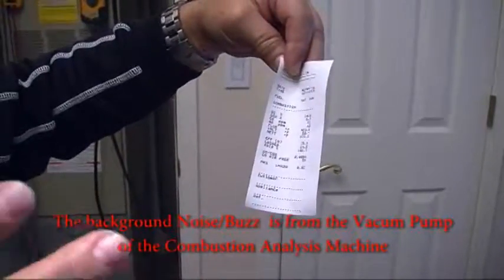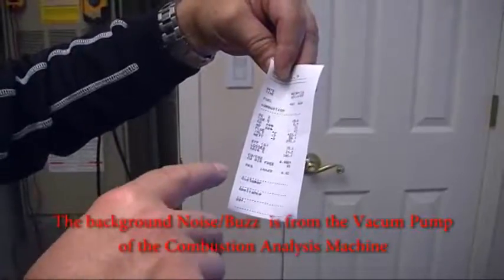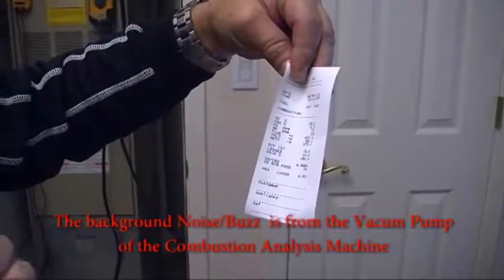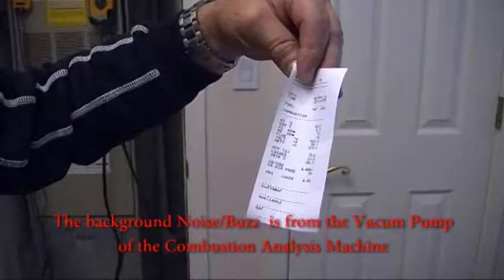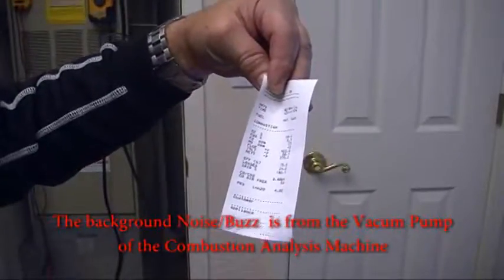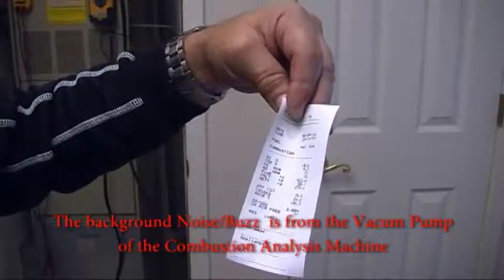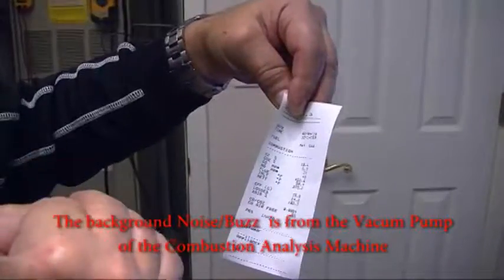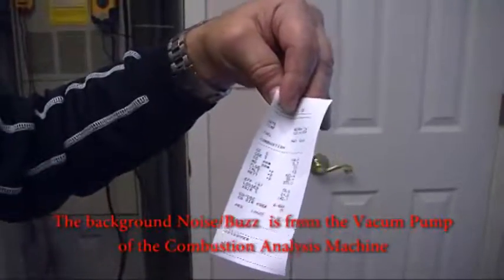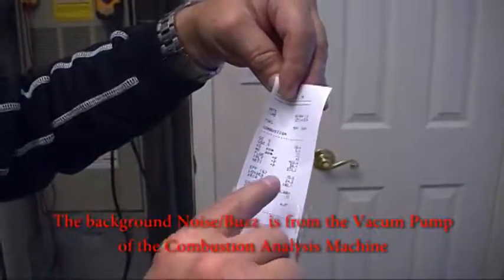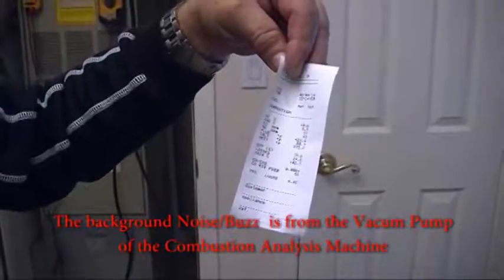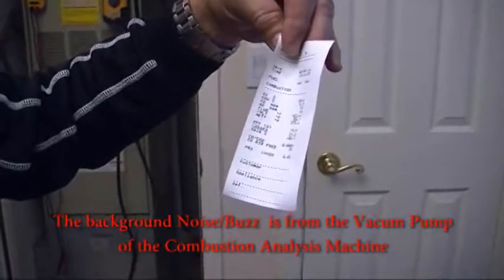The flue temperature plays a very, very big role in the carbon monoxide parts per million. The lower your flue temperature is on a standard non-condensing appliance, the higher your carbon monoxide is going to be. So our efficiency is 75.6 on a 20-year-old appliance.